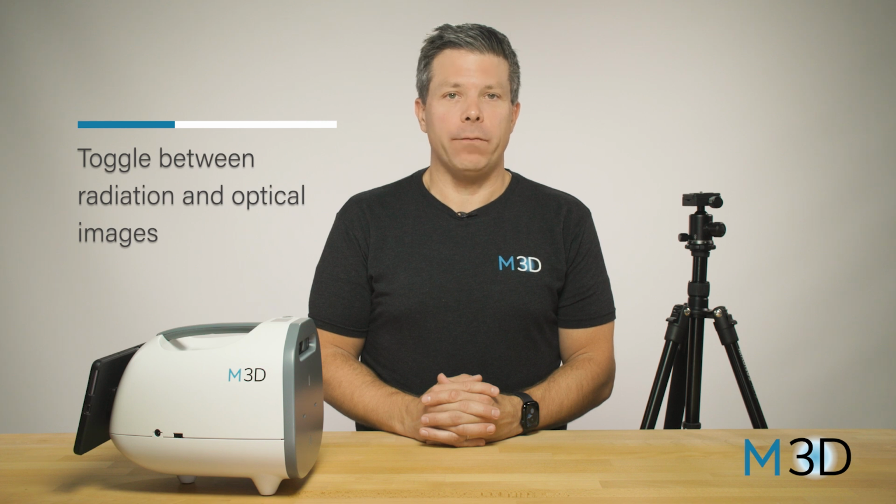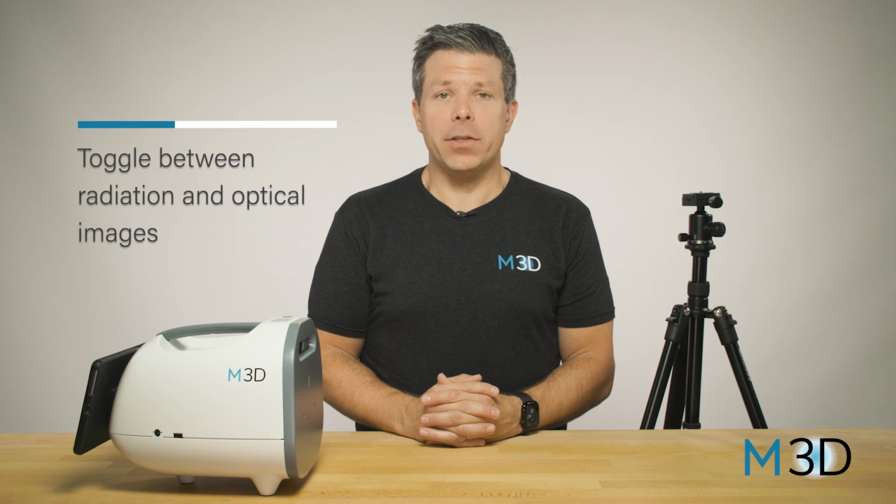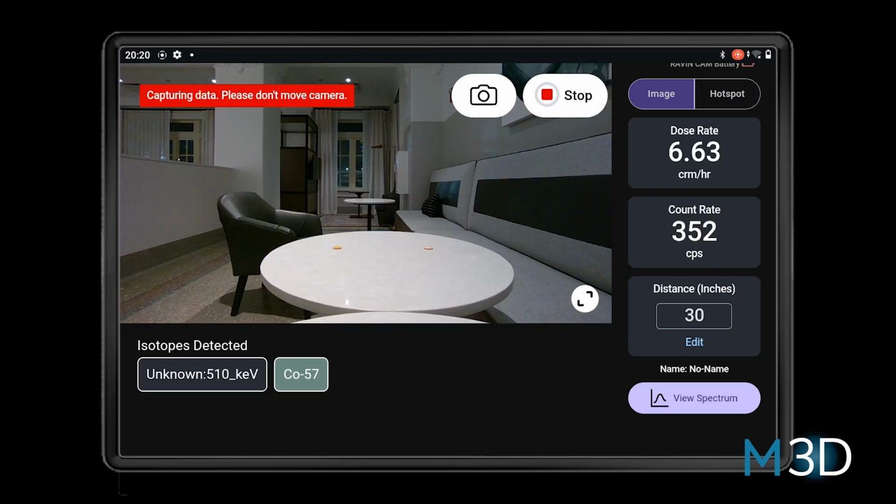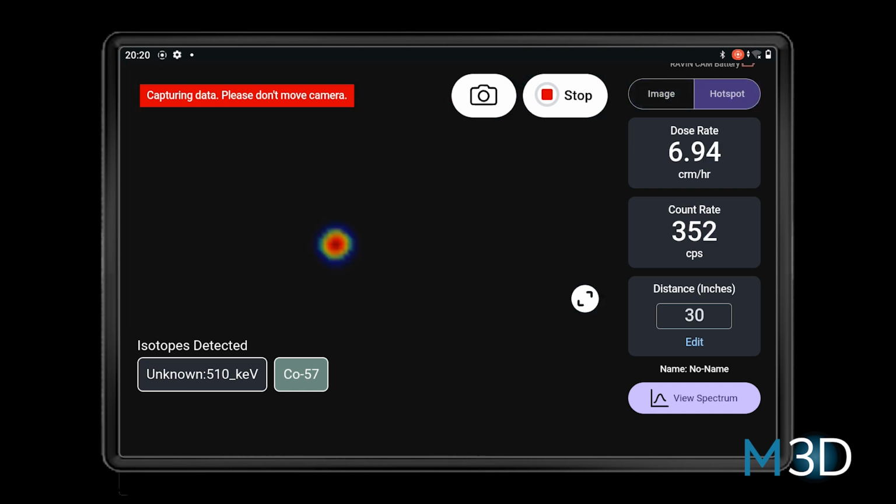Oftentimes, you may want to view only the optical image, removing the radiation image during a measurement. Or vice versa, where you only want to see your radiation image. Either way, use the toggle buttons in the upper right-hand corner of the screen.